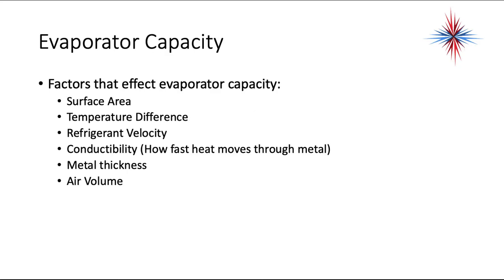Factors that affect evaporator capacity include surface area, temperature difference (delta T), refrigerant velocity, conductivity (how fast heat moves through the metal), metal thickness, and air volume. Air volume is important — systems are designed for 400 cubic feet per minute per ton. So for a 5-ton unit, that's 5 times 400, which equals 2,000 CFM.